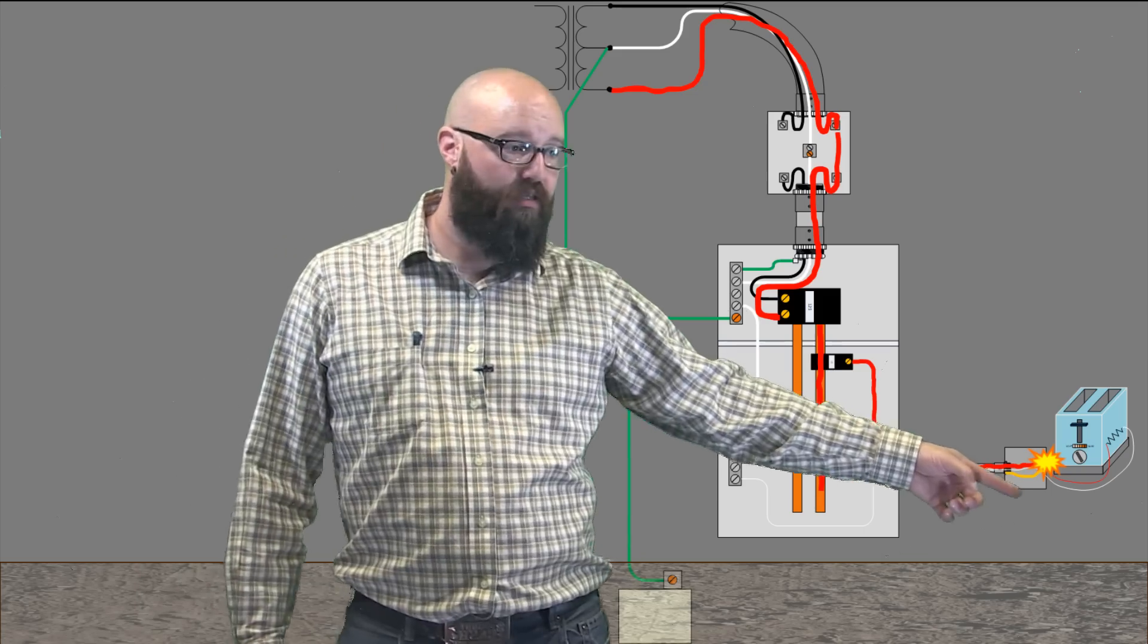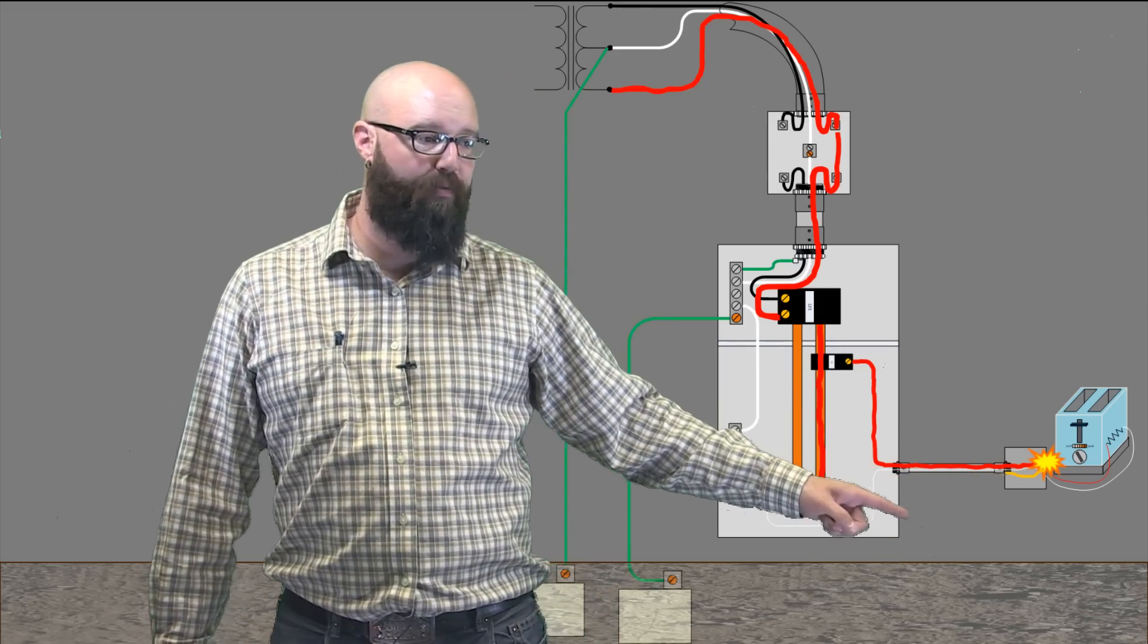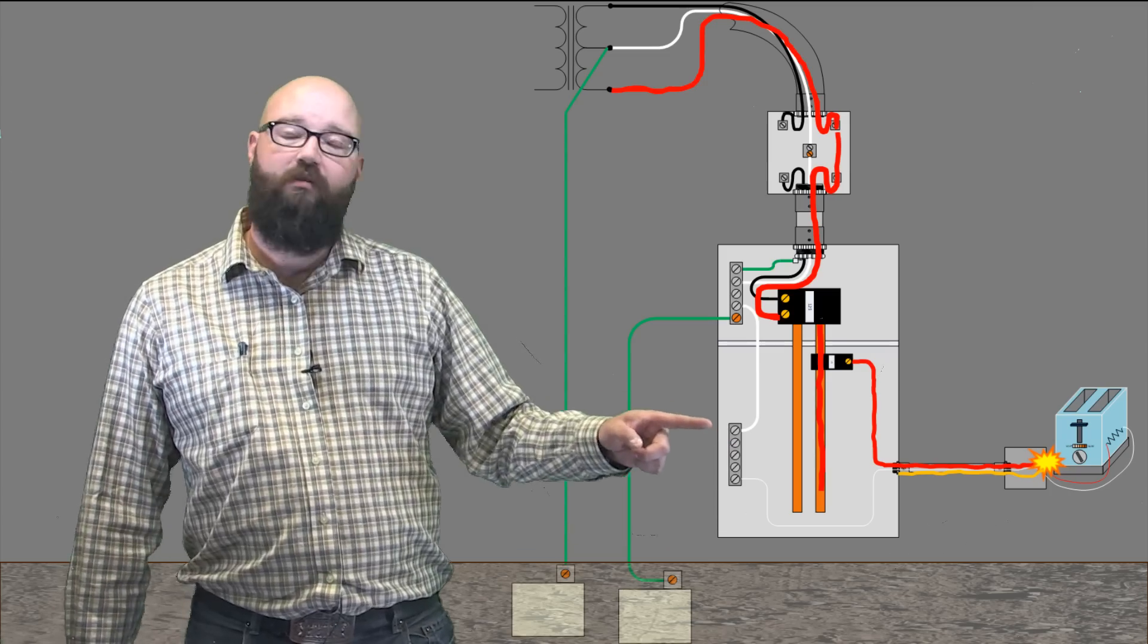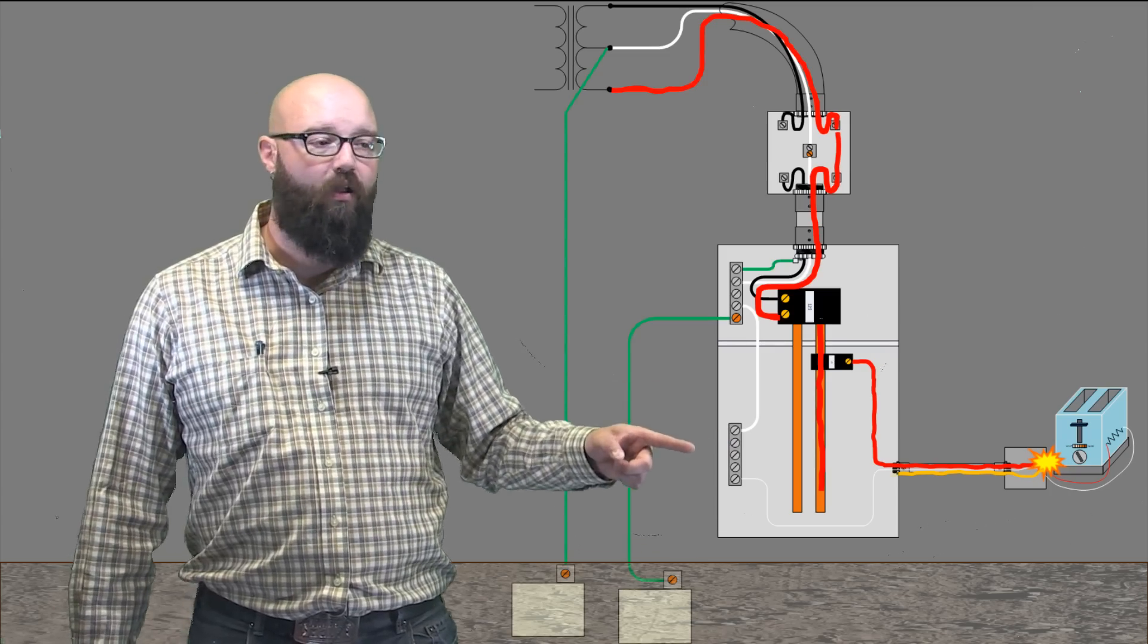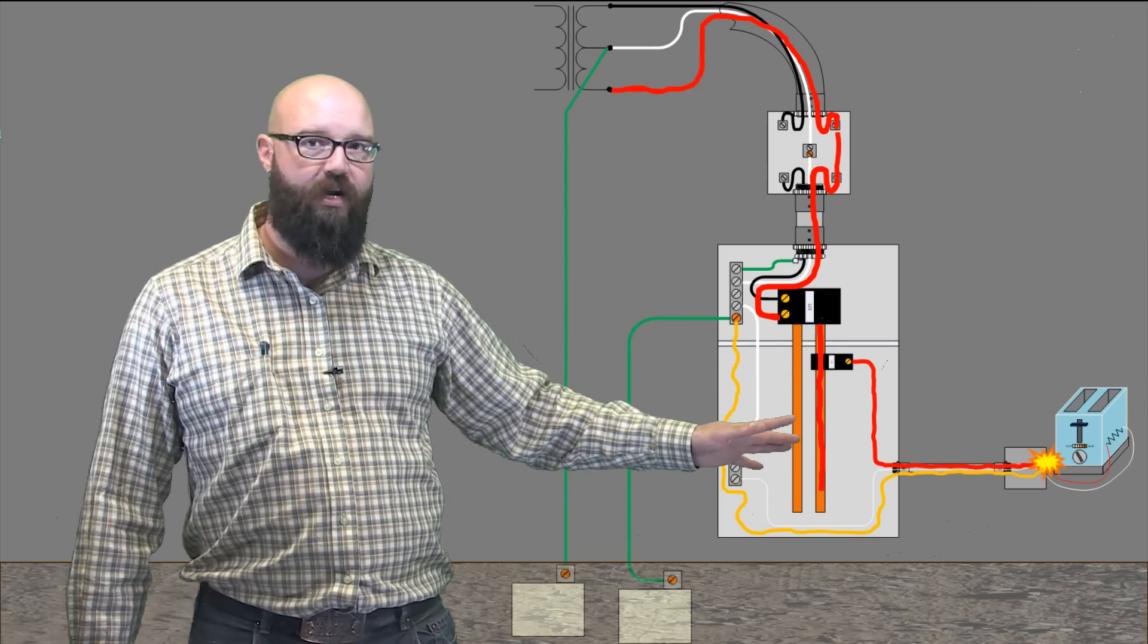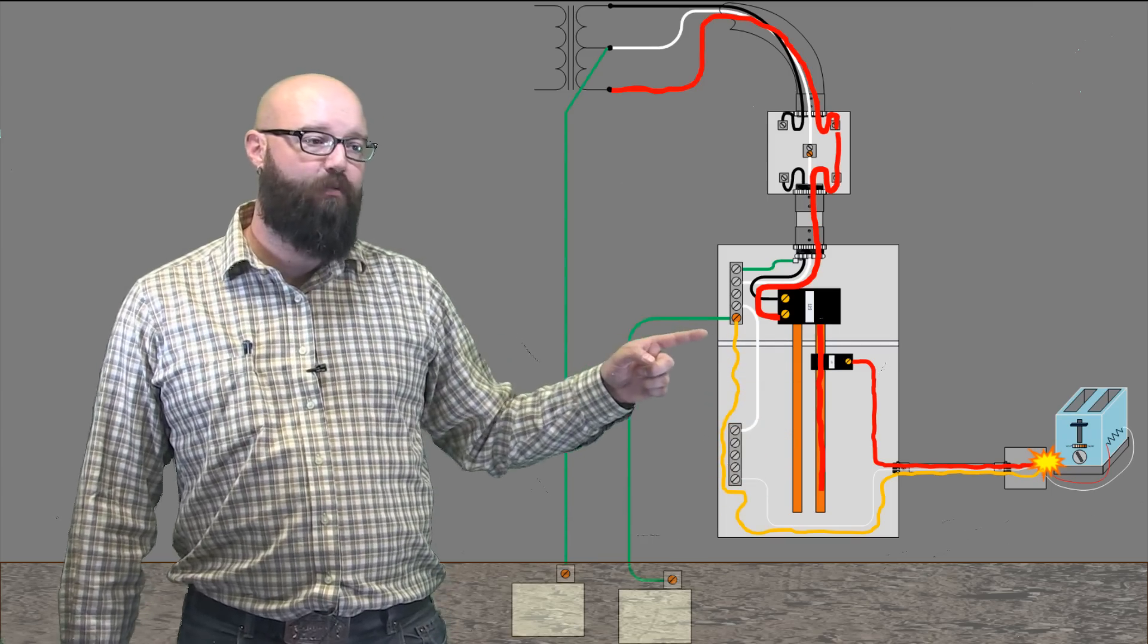So it comes back on the box, lock nuts and set screws are done up, makes its way back on this conduit, this panel is metal, and it conducts as well. So that fault current can make its way back in the actual panel. It's not going back on the identified anymore. And it gets to this point.